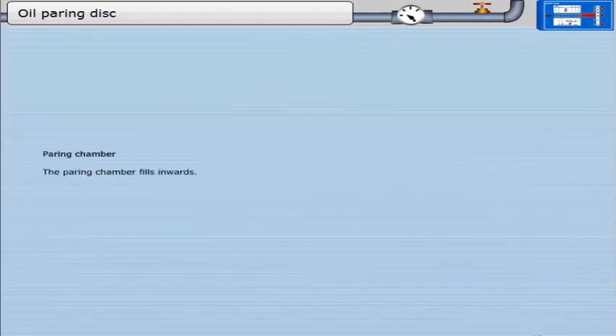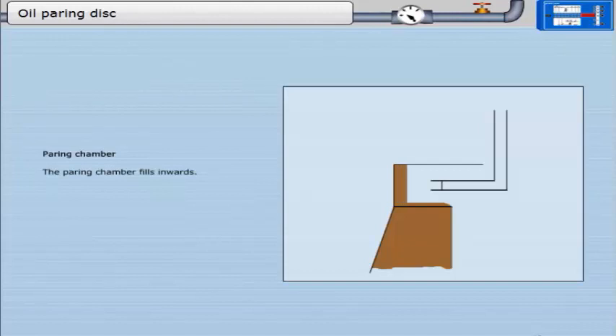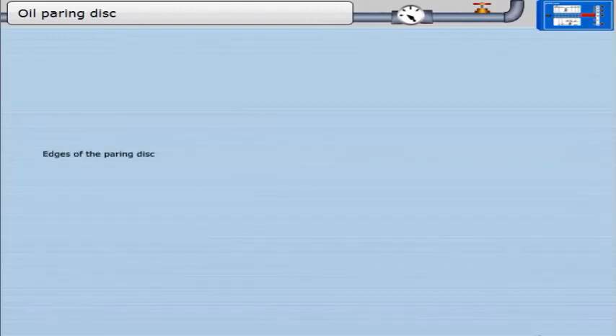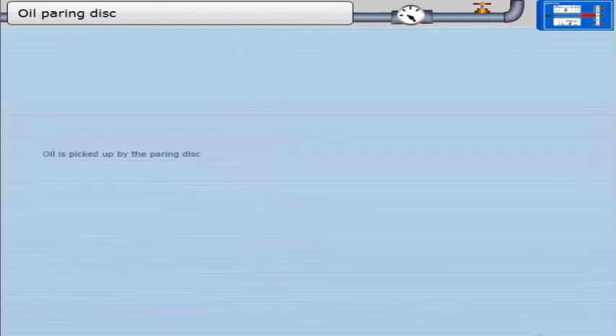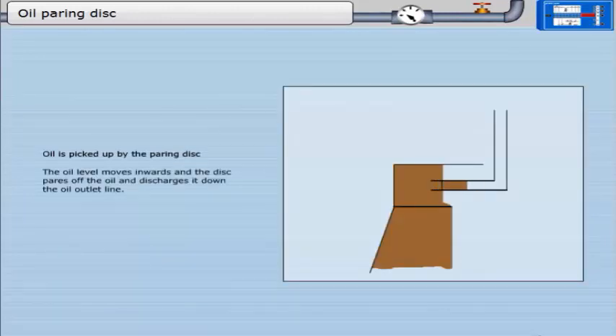The paring chamber fills inwards. The oil level reaches the top and bottom edges of the paring disc and an air seal is made. The oil is not picked up by the paring disc immediately, as the outer diameter of the volute is undercut. The air seal is to prevent any air being pumped out with the oil. Oil is then picked up by the paring disc, which pares off the oil and discharges it down the oil outlet line.